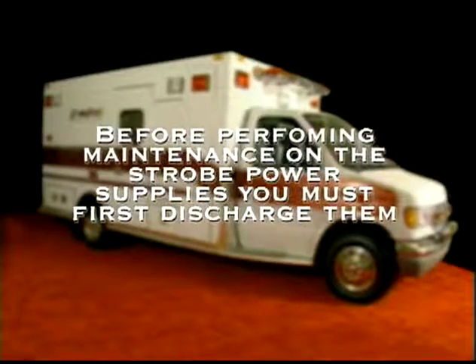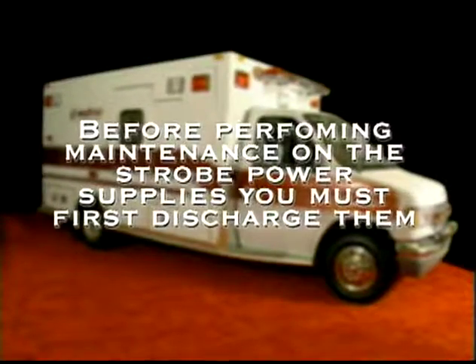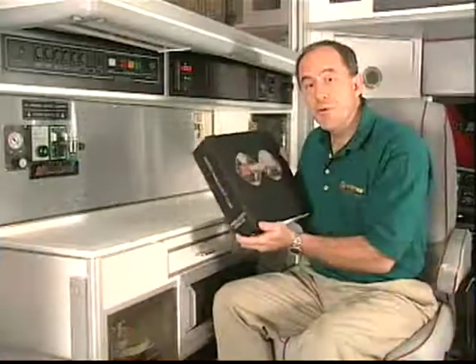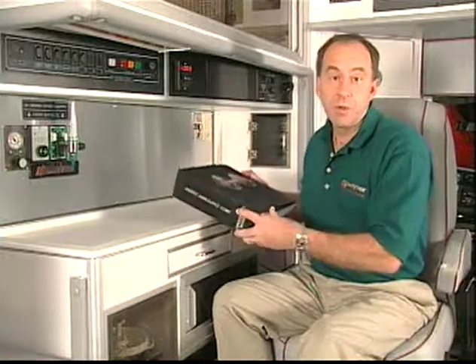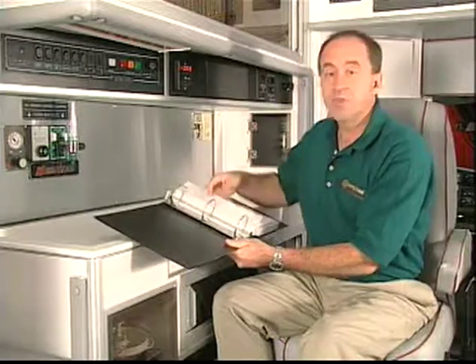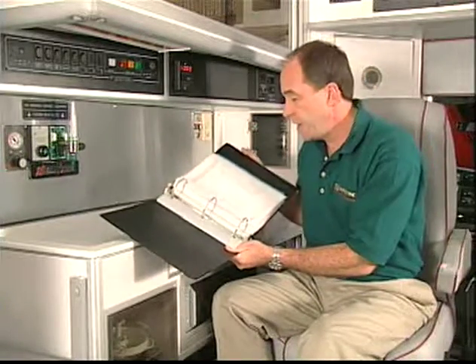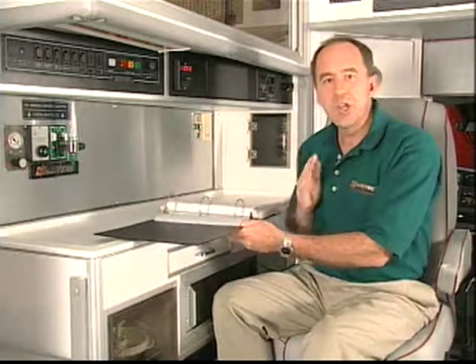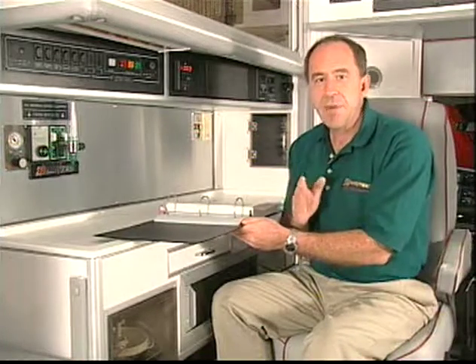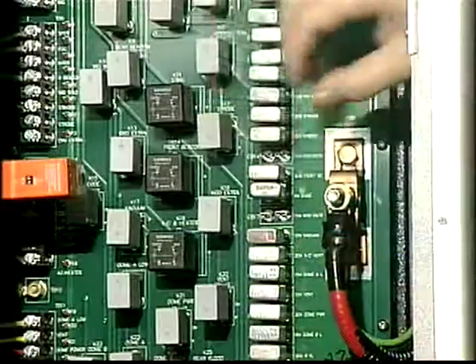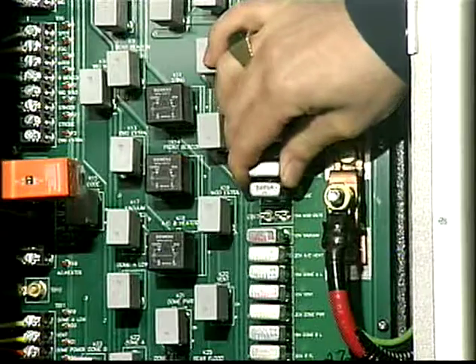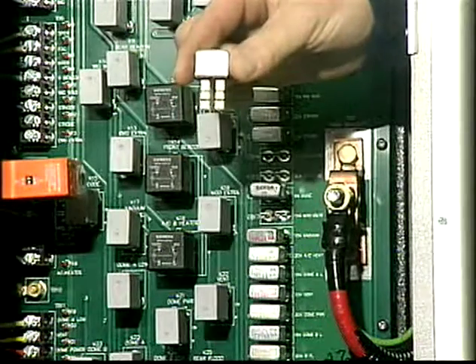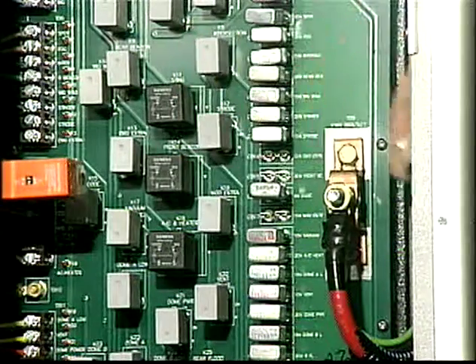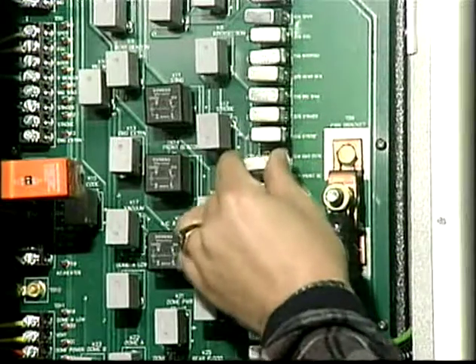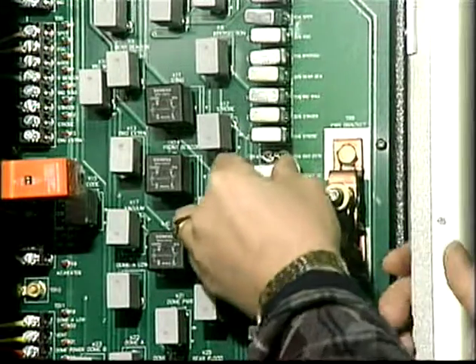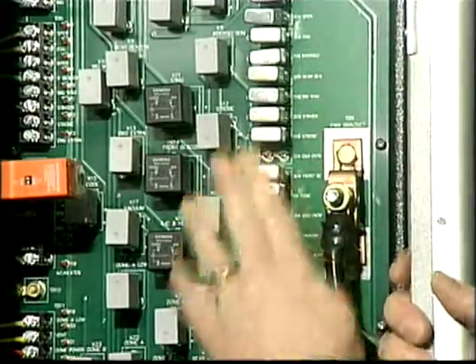Before performing maintenance on the strobe power supplies, you must first discharge them. Refer to your ambulance electrical manual for diagrams to aid in troubleshooting your electrical problems. If you have difficulties locating an electrical problem, MedTech Service Department can help. Electrical relays and circuit breakers are removed by grabbing the relay or breaker and pulling it straight out. Replacement is made by properly aligning the new one and pushing into the terminal slots.